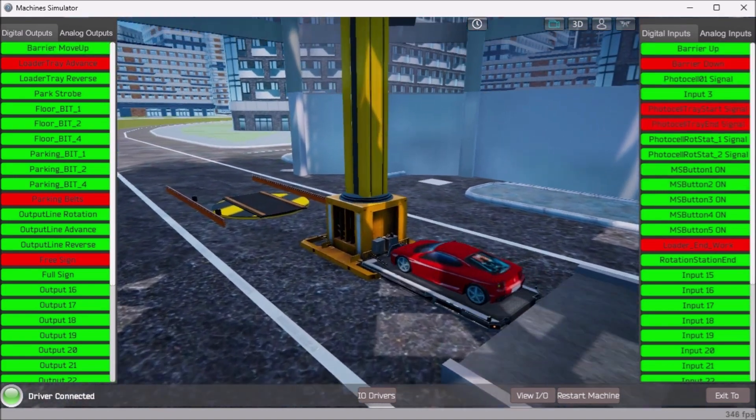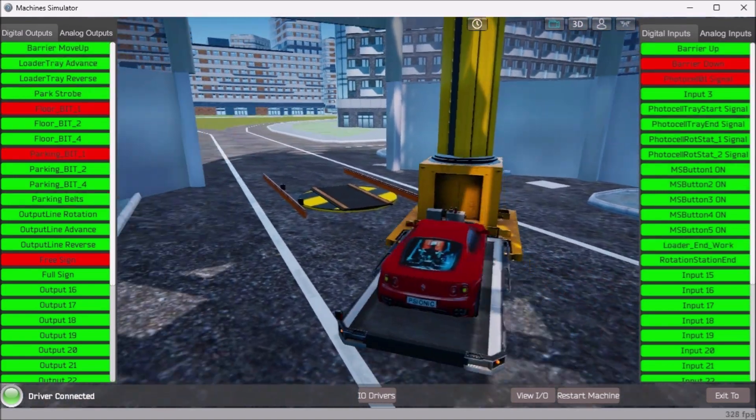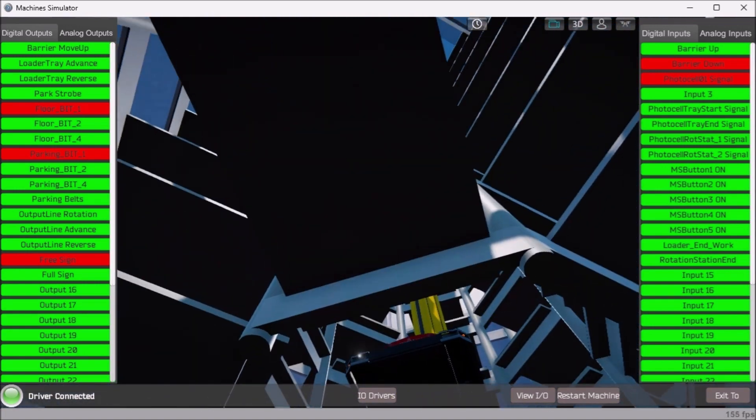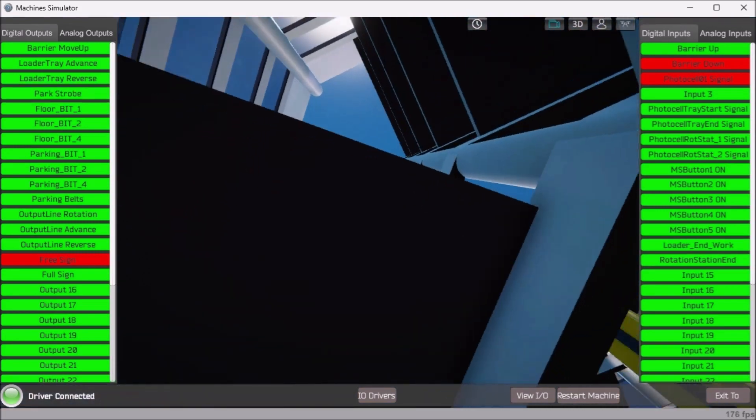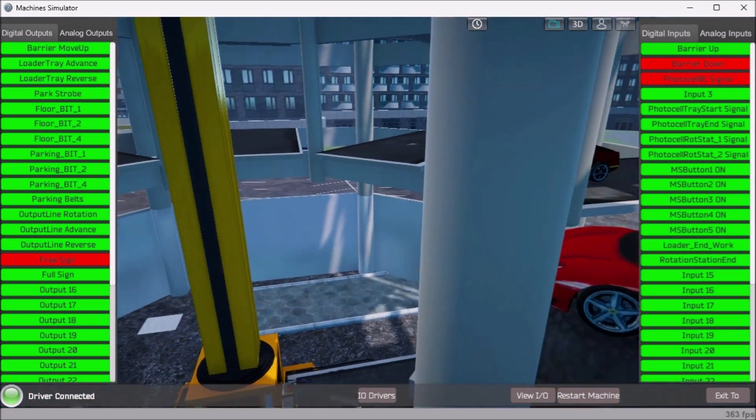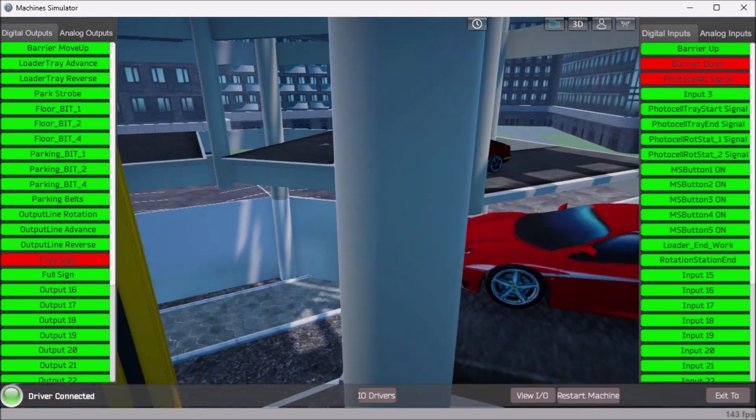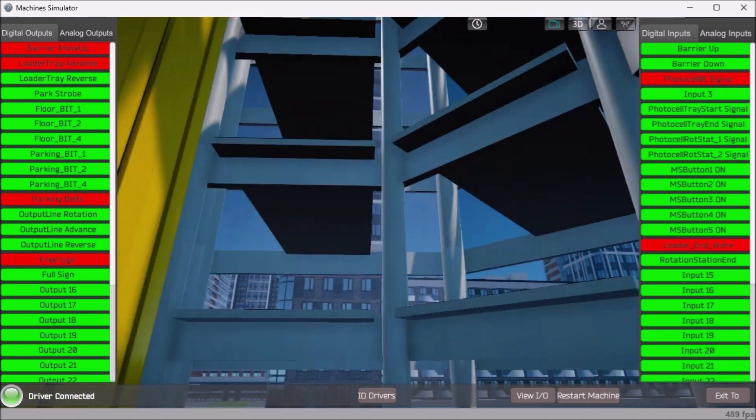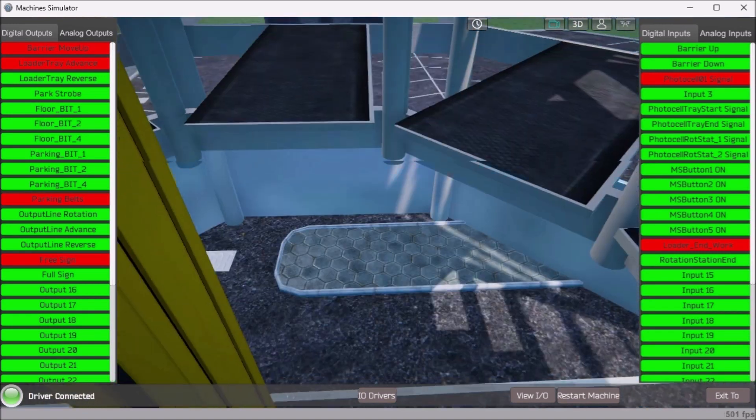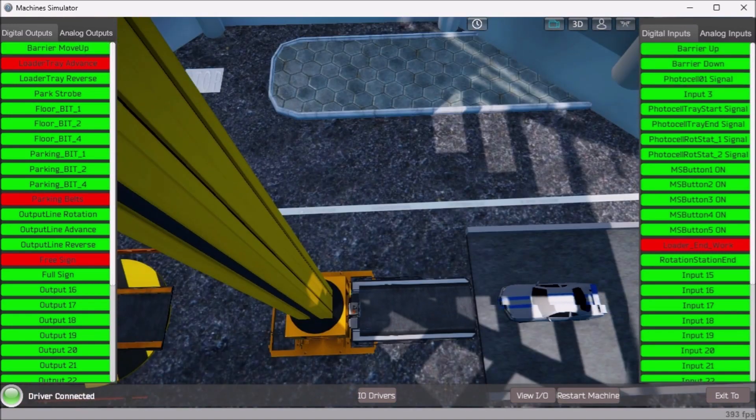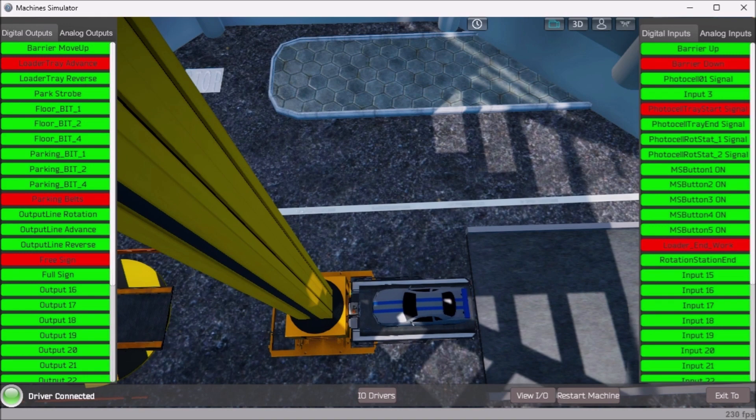Move around this easy PLC machine environment and try to account for when sensors fail. This is all part of program testing. You may have to rewrite your ladder logic code if something unexpected happens. This may even mean that you have to go back and change the operational sequence.